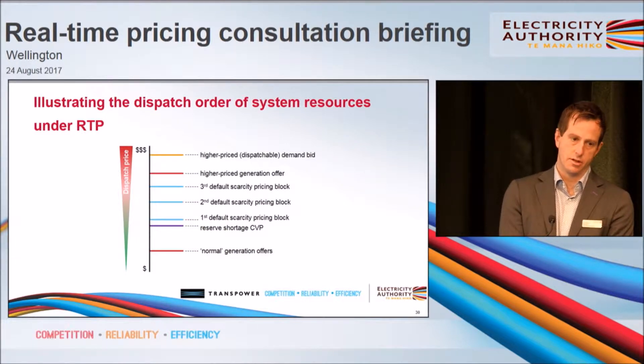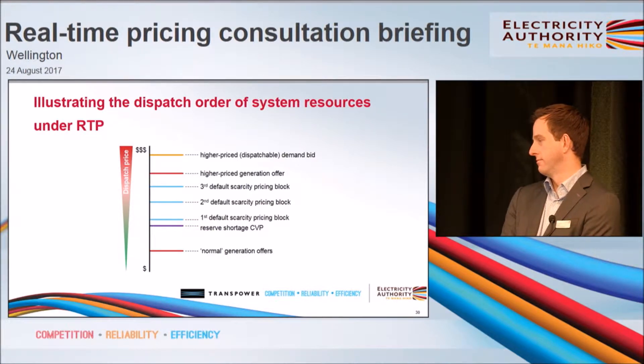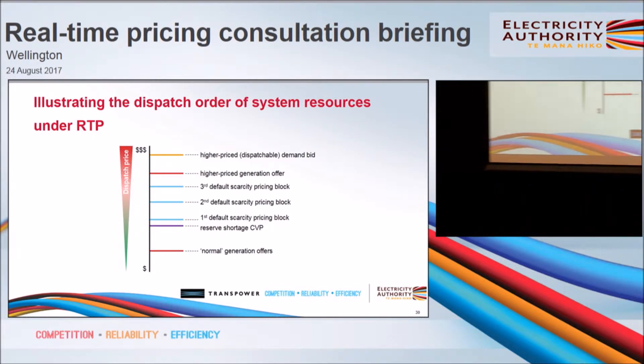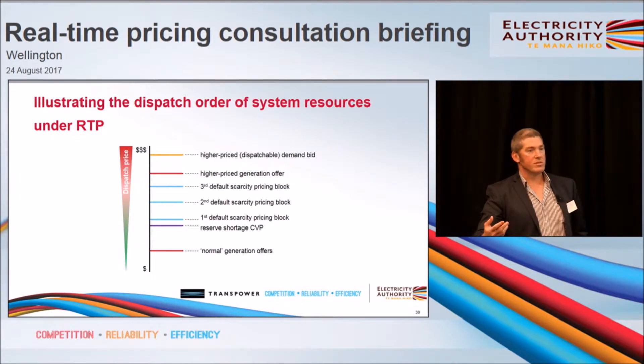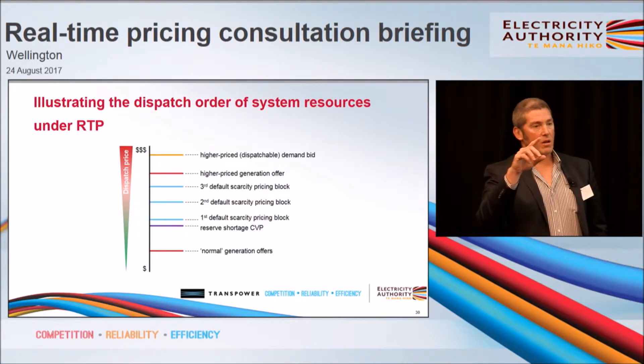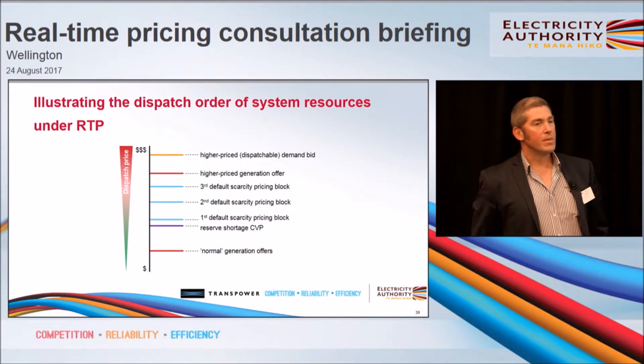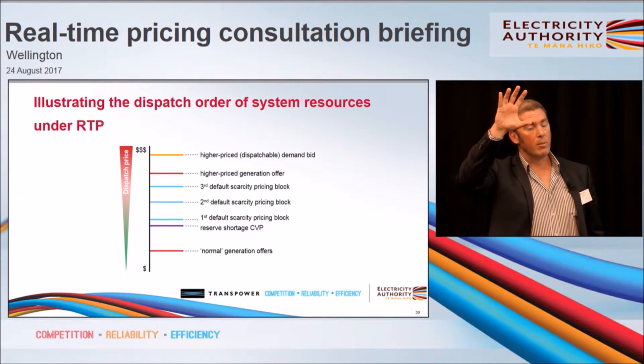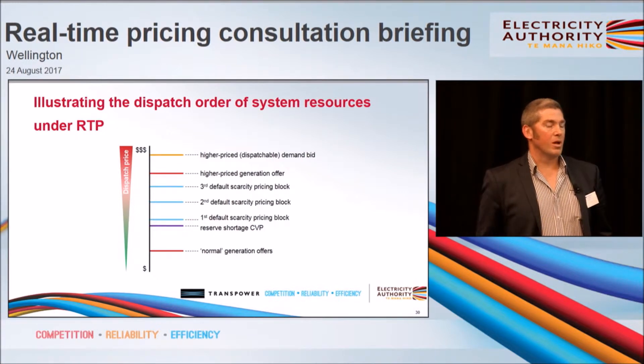Potentially, if it's an unconstrained generation shortage situation, then logically that would be the case. Murray: Just going back to the earlier point — if it's an island-wide issue, certainly in the first instance until everyone's got some learned experience of real-time pricing, our expectation is we would still ask load to disappear at the larger centres where it can disappear without people noticing to the same extent, rather than always kicking Northland when they're down. But the pricing impacts would be as described. In terms of where the load is shed, that's still targeting the large municipal centres first, because ripple control in Auckland can make a lot of load go away, which people don't notice for the short periods of time.